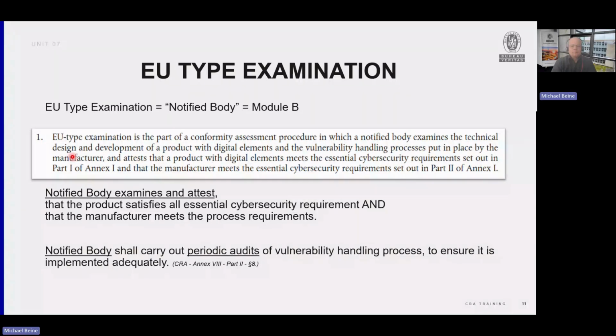Again, the notified body looks at the requirements from part 1 of Annex 1. That means he will look into the essential cybersecurity requirements of products. Does the product meet the requirements, but also look into the process requirements. And this is a little bit different to RED. In the Radio Equipment Directive, the notified body only looks at the product requirements or product properties.